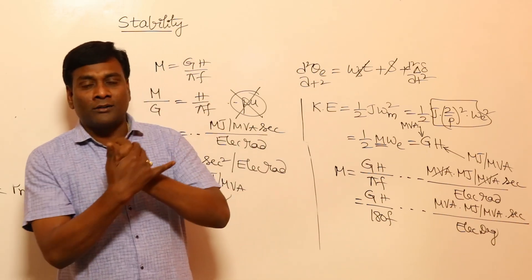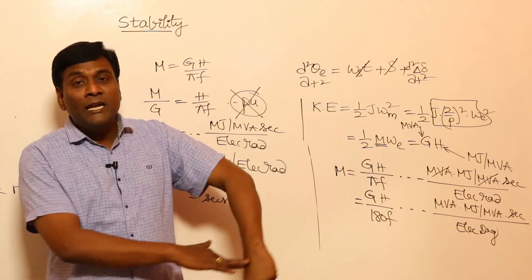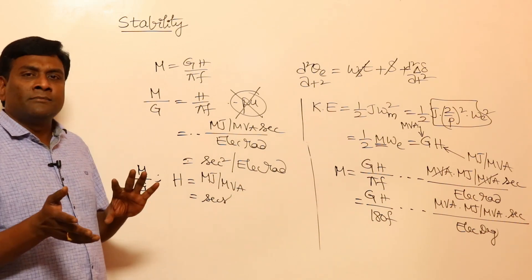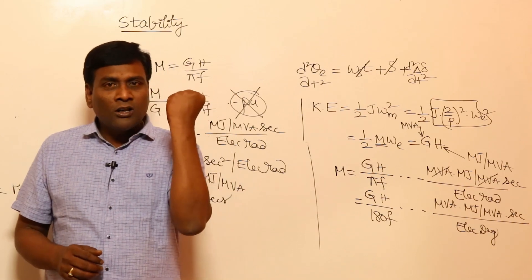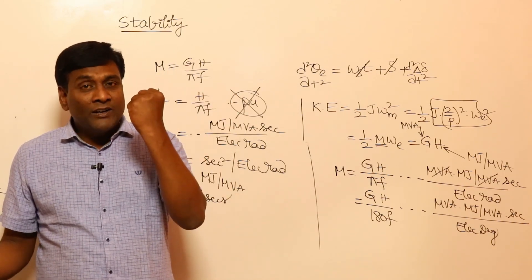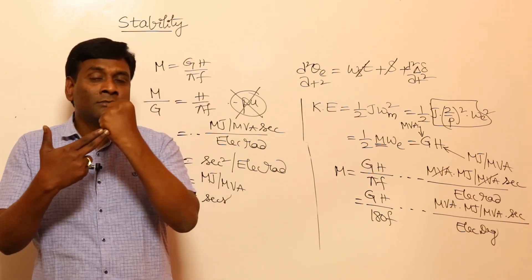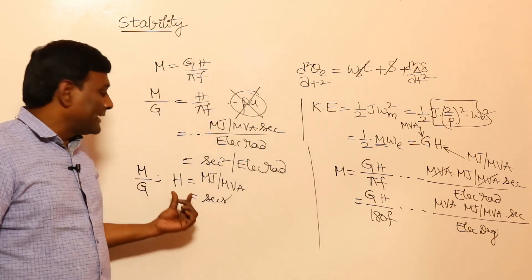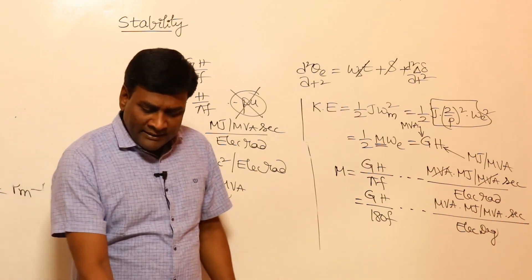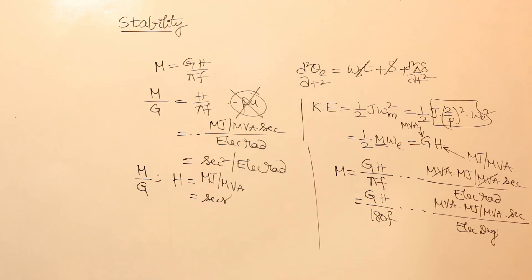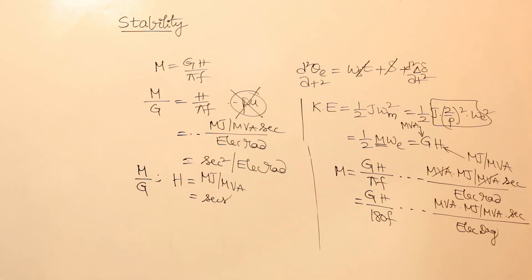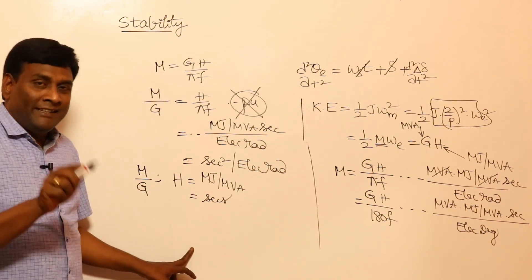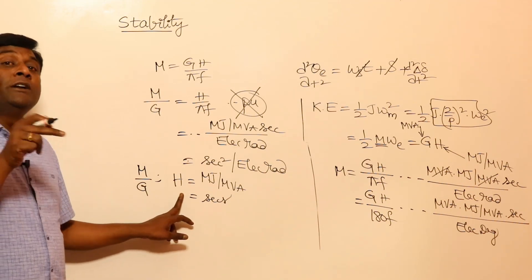Alternatively, H is the time for a rotor spinning at synchronous speed to come to standstill when rated opposing torque is applied. To summarize: M per unit really means M per unit of MVA (= M/G); H per unit really means H per unit of MVA. H is in seconds; M is in mega joule·seconds per electrical degree. These are dimensional quantities, not true per-unit values.